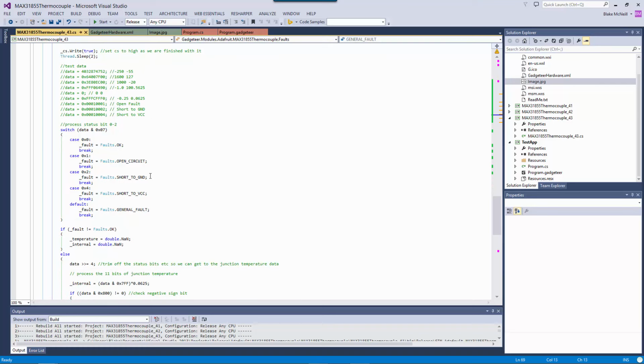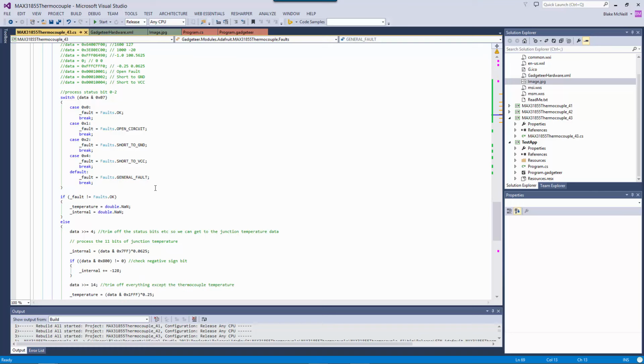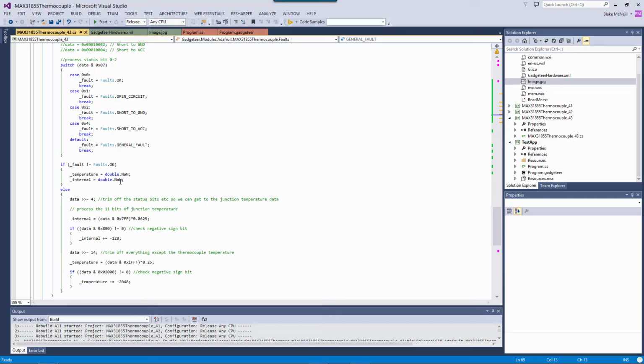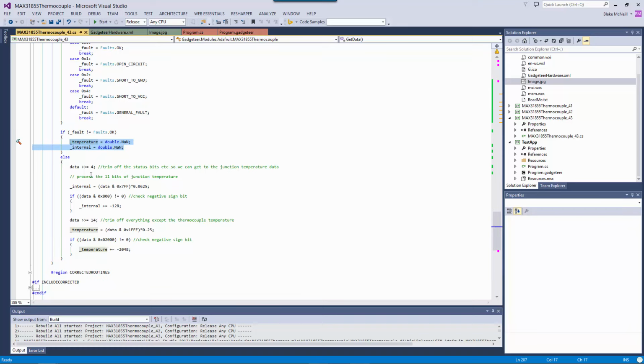So we come in here — the first 3 bits in our data are fault indicators. The chip is able to give us back information on whether or not there were faults. If we get anything other than a no-fault condition, we just set our internal and thermocouple temperatures to not-a-number. Then we peel off those 3 bits and another bit, which is just a reserved bit.